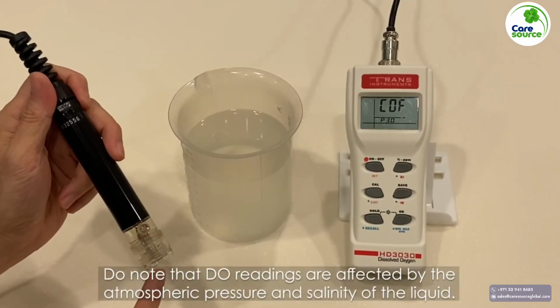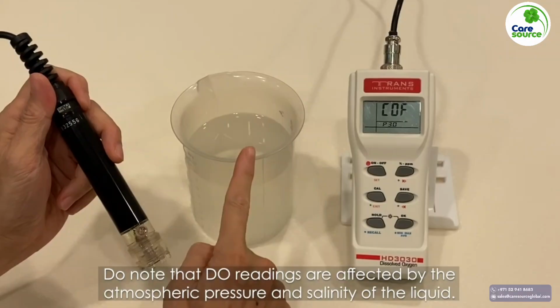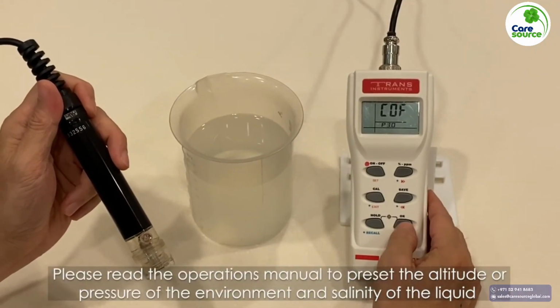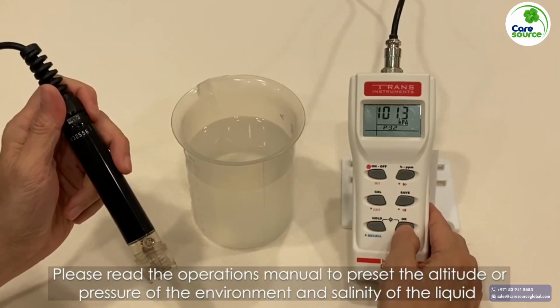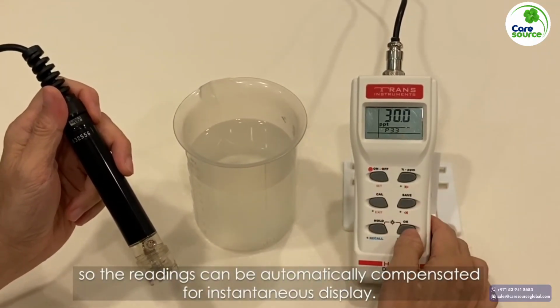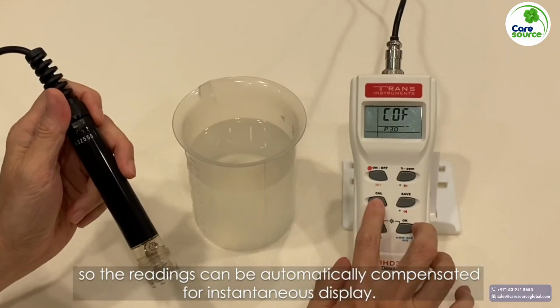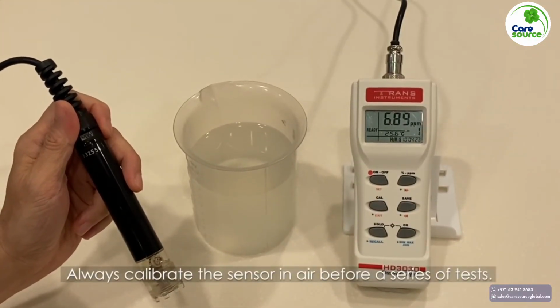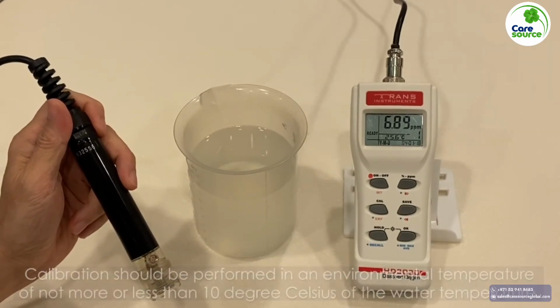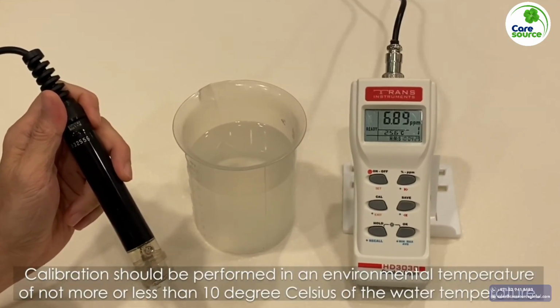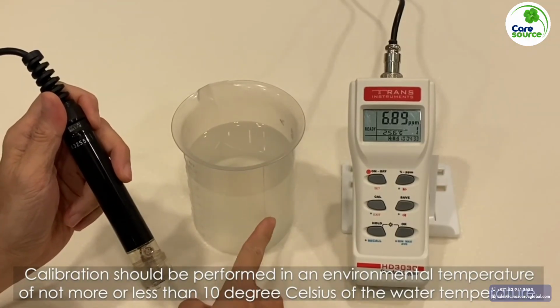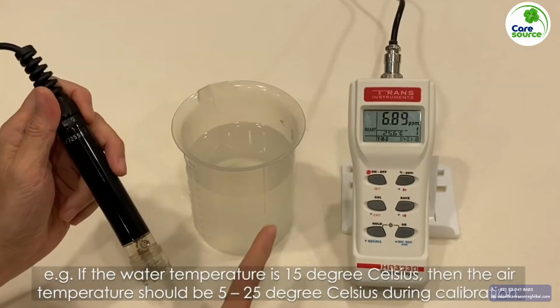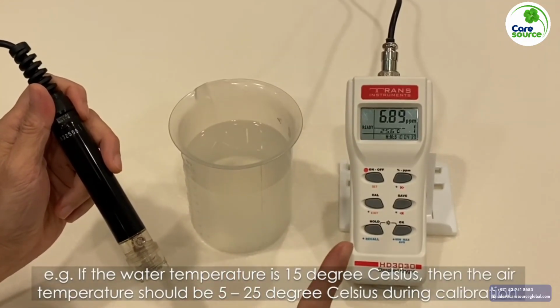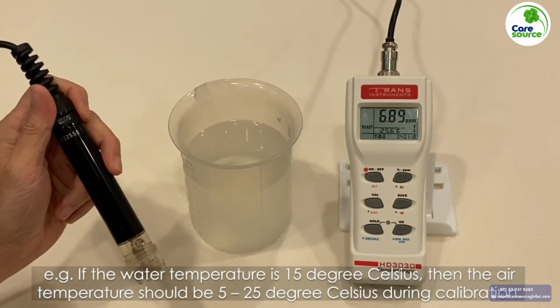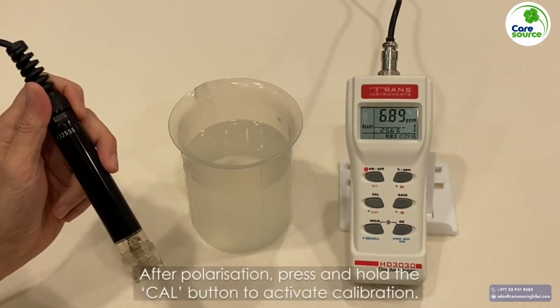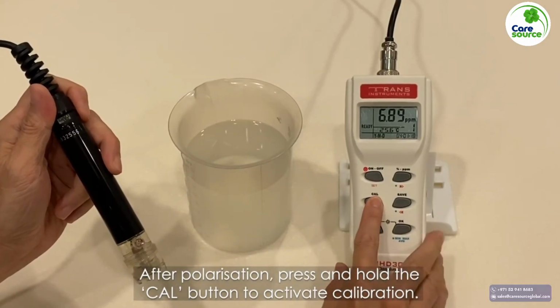Do note that DO readings are affected by the atmospheric pressure and salinity of the liquid. Please read the operational manual to preset the altitude or pressure of the environment and salinity of the liquid so the readings can be automatically compensated for instantaneous display. Always calibrate the sensor in air before a series of tests. Calibration should be performed in an environmental temperature of not more or less than 10 degrees Celsius of the water temperature. Example, if the water temperature is 15 degrees Celsius, then the air temperature should be between 5 and 25 degrees Celsius during calibration. After polarization, press the Cal button to activate calibration.